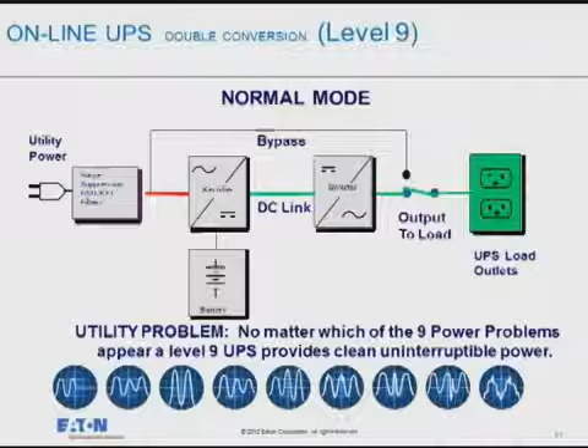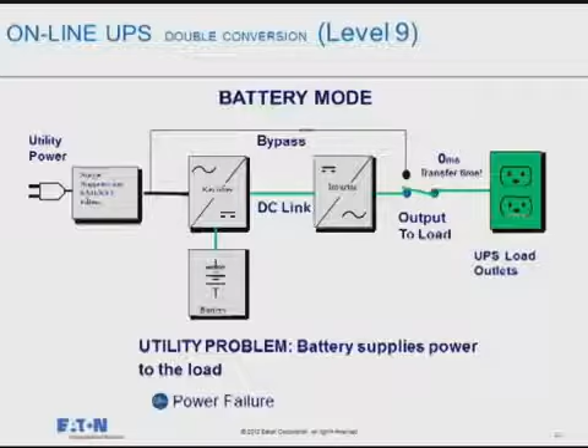Two things: it's not switching the load. The load is always fed off of an inverter. It's an internal switching, so there's no impact, no transfer time to the load. But more importantly, this is only used when it can absolutely no longer clean up the power. So we have scenarios where we have 84 volts, 85 volts coming out of the utility or out of the wall plug, and the UPS is creating 120 without using the battery. It'll run forever in that condition. So by not using slices out of the battery, we extend the life of the battery. Typically on an online double conversion, you're going to get 5 years plus out of the battery.